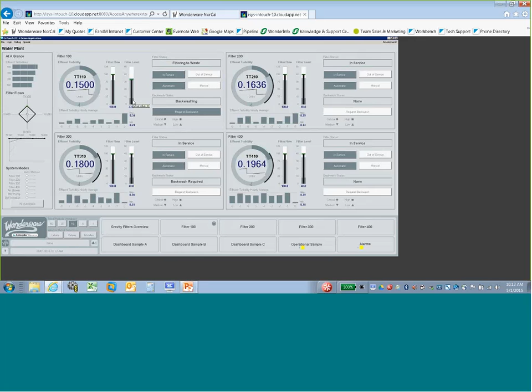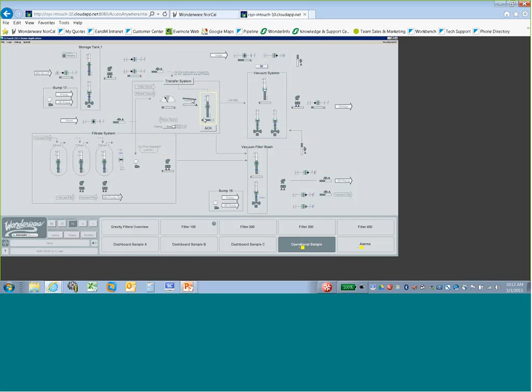I've got some other situational awareness graphics here that show me my desired set point in green. I can see where I'm real-time at in comparison to my set point, and then I can see if I were to go into a low limit that I would get an alarm border to pop up. An example of that would be in this operational sample, again making it very intuitive. I can see I've got a level 2 priority alarm here that's blinking, so I can go drill down to that - I could drill down into a specific filter here.